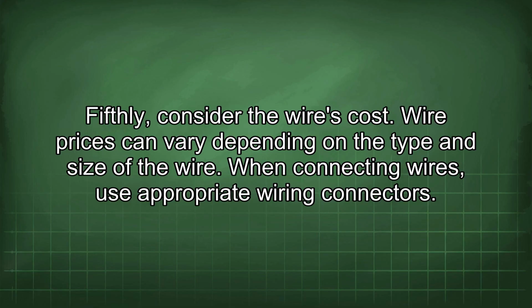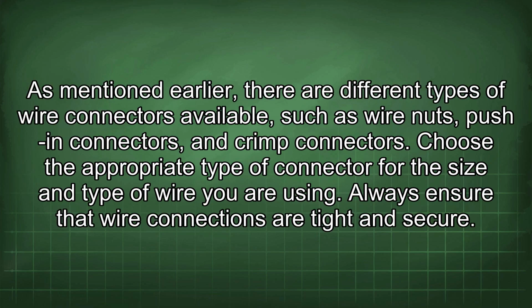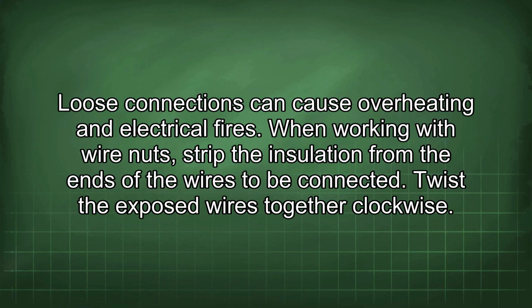When connecting wires, use appropriate wiring connectors. As mentioned earlier, there are different types of wire connectors available, such as wire nuts, push-in connectors, and crimp connectors. Choose the appropriate type of connector for the size and type of wire you are using. Always ensure that wire connections are tight and secure. Loose connections can cause overheating and electrical fires.